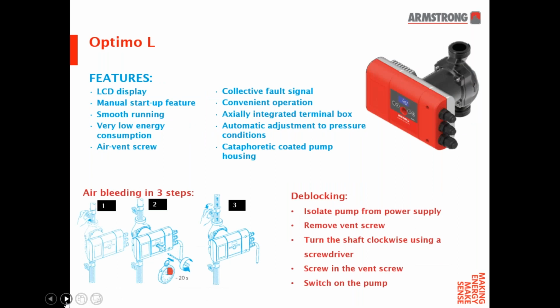So the features of the L: an LCD display, manual startup feature, smooth running. The A-rated motor gives you very low energy consumption. As I've said, the air vent screw, collective fault signal, convenient operation, axially integrated terminal block, automatic adjustment to pressure conditions within the system, and a cataphoretic coated pump housing. Again, even though the format of the display is slightly different, air bleeding is exactly the same as previously described with the Optimo and the Optimo Basic.